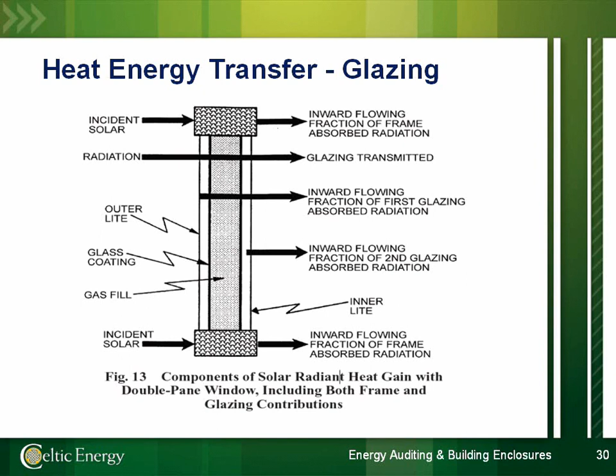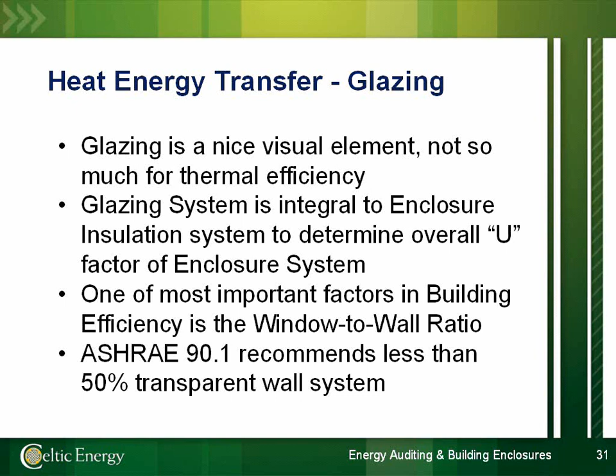It's important to recognize that glazing is part of an overall wall assembly. If you want a high-performance building, you need to look at it holistically, including the opaque wall elements as well as the quantity and quality of the glazing systems. Many glass buildings, nearly all glass buildings, are visually stunning but from an energy standpoint quite inefficient. There is more and more attention being paid to the wall-to-window ratio, as awareness created by the U.S. Green Building Council and others of building efficiency and effectiveness has begun to influence the design community.